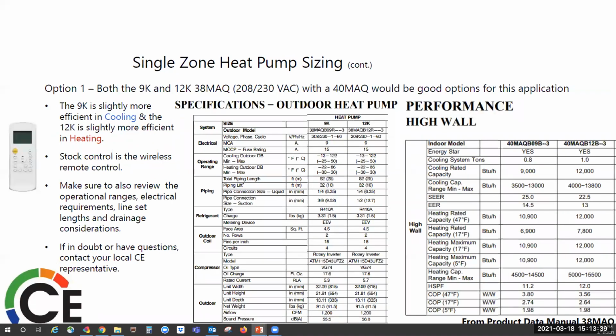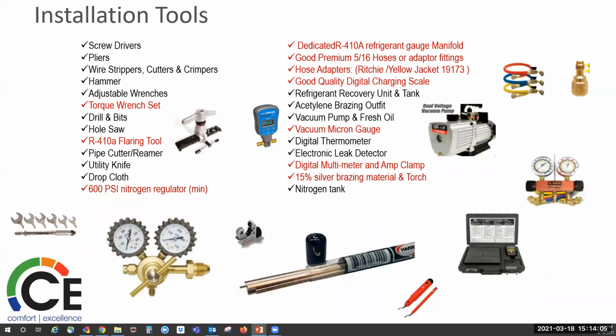You also must take into consideration the location of the indoor unit, making sure you get the best coverage, and the location of the outdoor unit to prevent damage from ice and snow. Consider drainage: whether a condensate pump is needed or you're going to go gravity. Wireless remote, wired controller, 24-volt interface, Wi-Fi: you want to think about all those. And we're going to move right into installation tools.